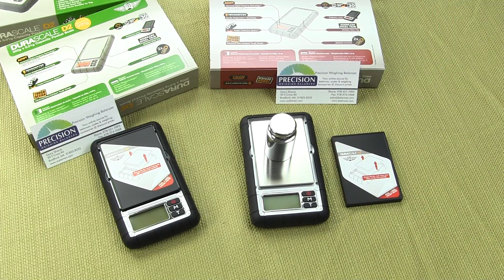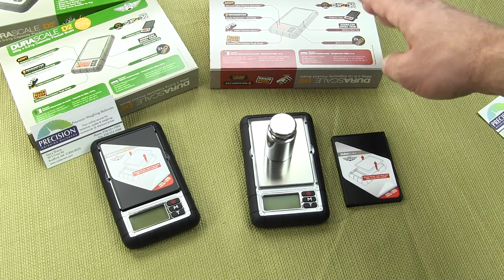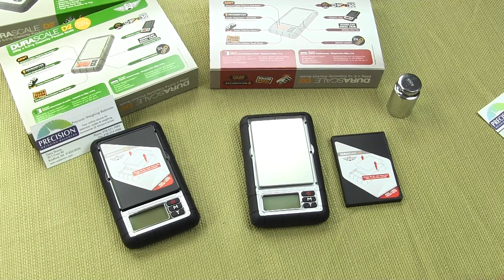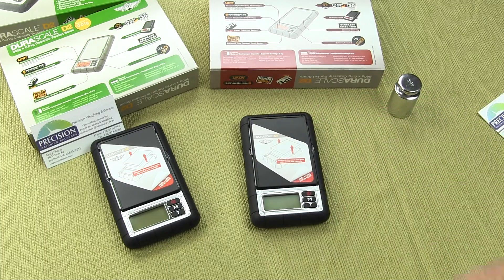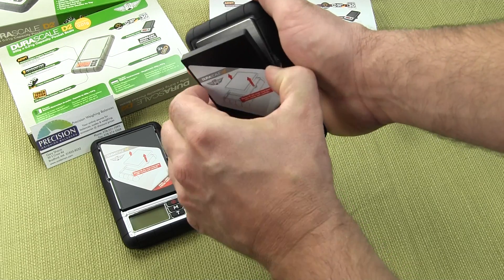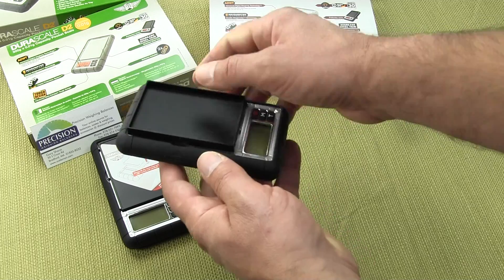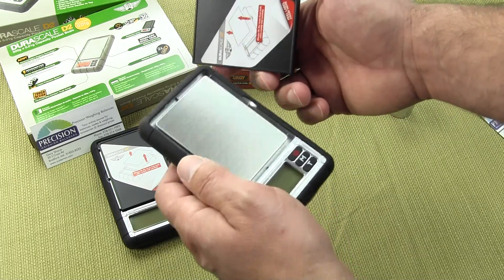Let's go over some of the features. On the right hand side we have the 600 gram unit. First, the scale offers a protective cover when it's delivered. This cover needs to be removed altogether before use — if you leave this cover on, you're not going to be able to weigh anything. The cover protects the scale and you can also invert it so that it acts as a weigh-in tray. My Weigh has done a great job in everything that they designed.